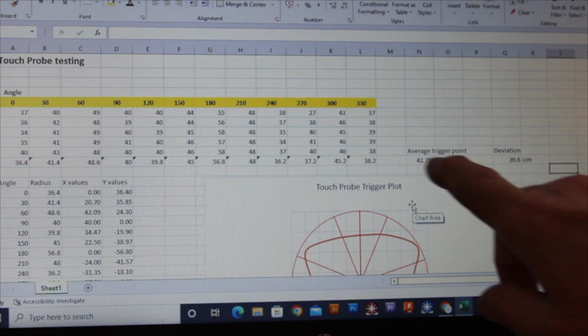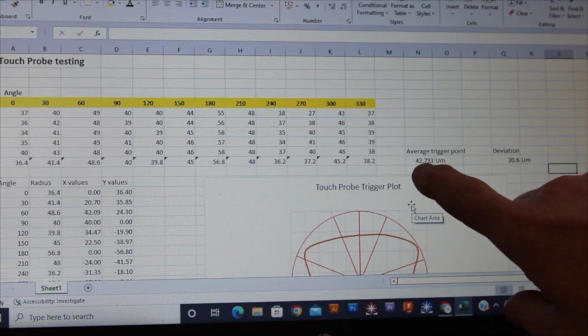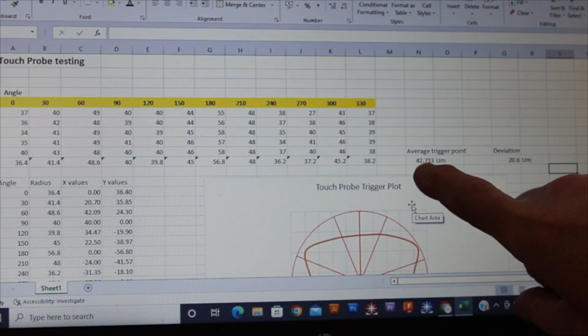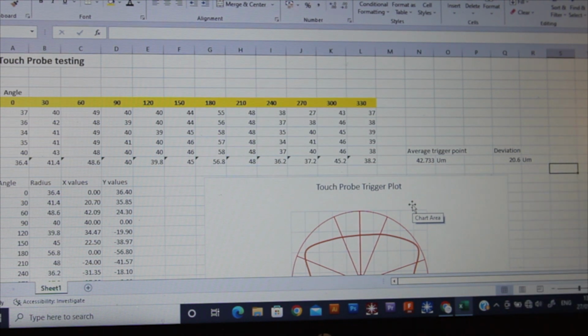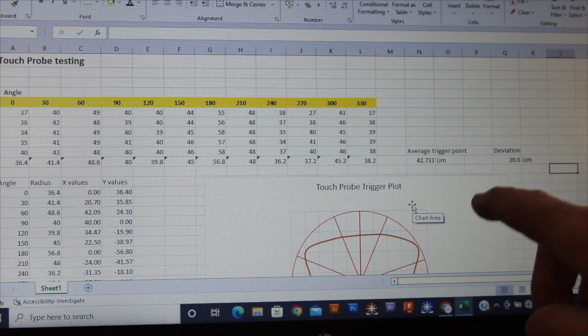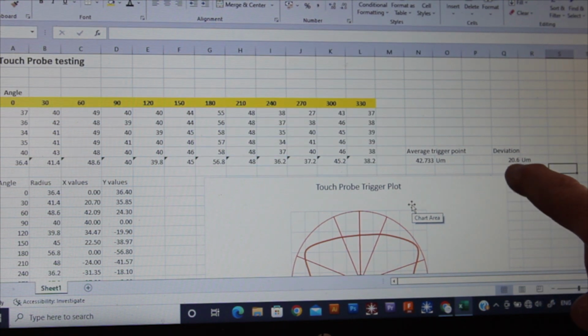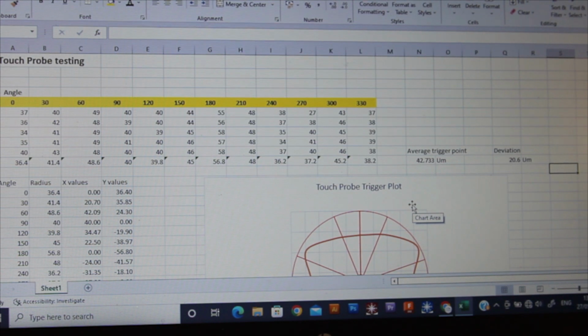And from that I've averaged them all, the average of averages, and the average trigger point is 42.733 microns, and the deviation between the maximum and minimum is 20.6 microns.